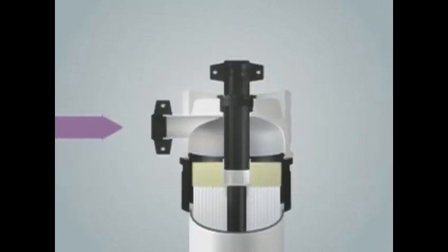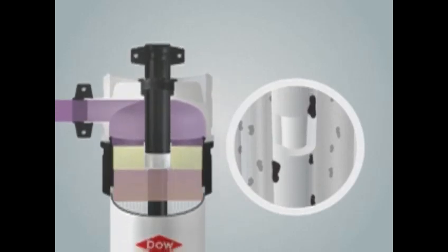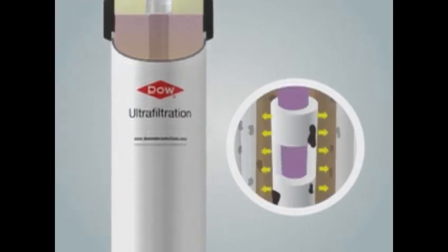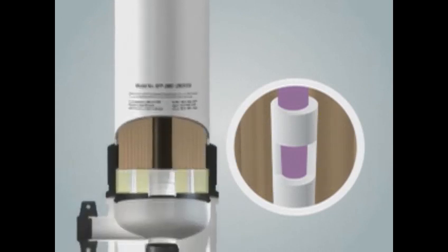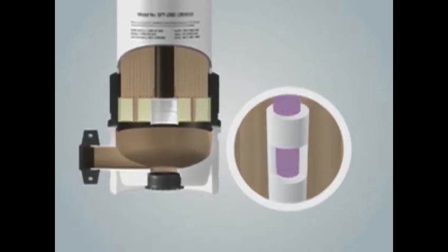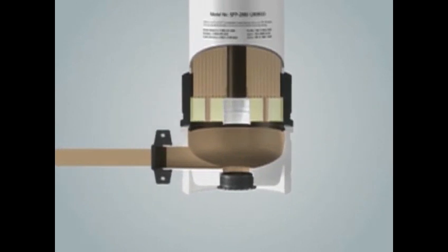Occasionally, a module requires chemical cleaning to restore its performance. This step is referred to as a chemically enhanced backwash, or CEB. The required frequency to conduct CEB varies and depends on feedwater quality.